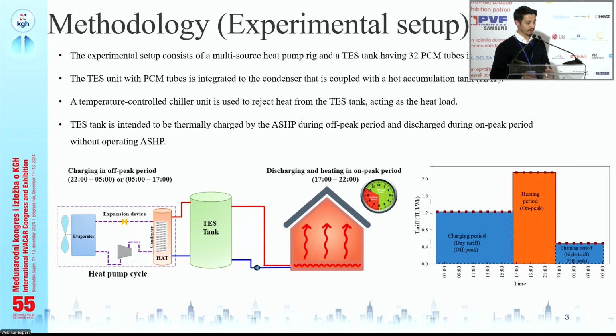The thermal energy storage with PCM is integrated, as I said, to the condenser unit of the heat pump, and the condenser of the heat pump is coupled with a hot accumulation tank. A chiller unit is used to reject the pre-stored heat from the thermal energy storage unit, which simulates the heating load, such as a building. And of course, I have to add that the electricity prices are charged very high in the on-peak periods in order to encourage people to use electricity during the off-peak periods.